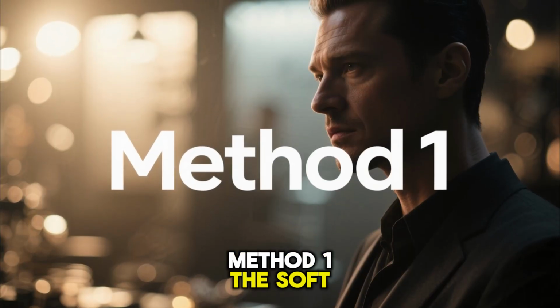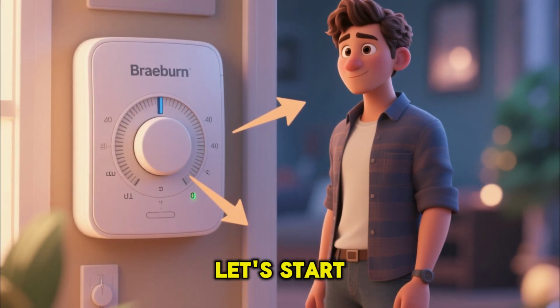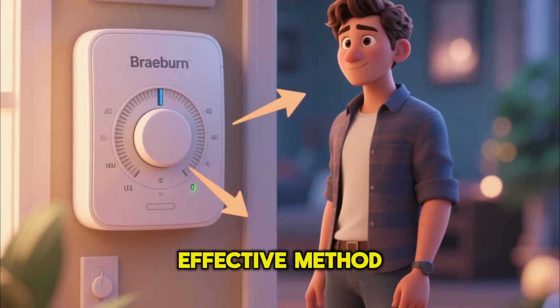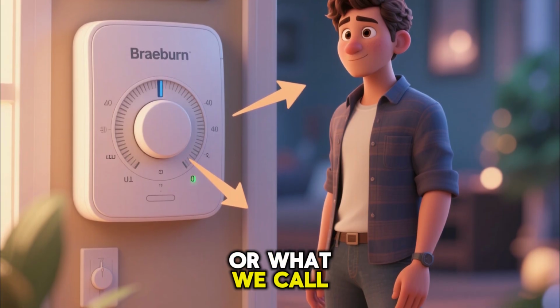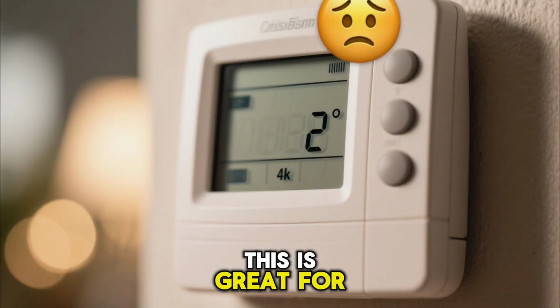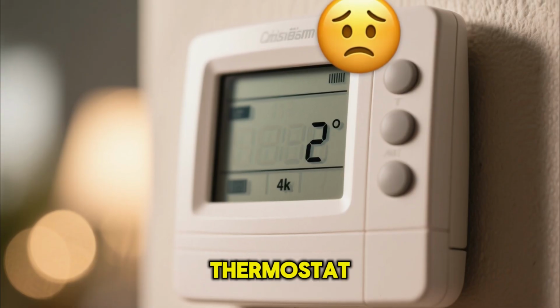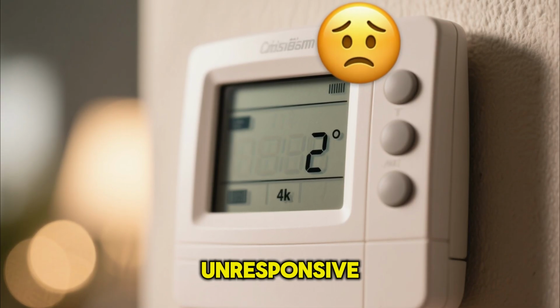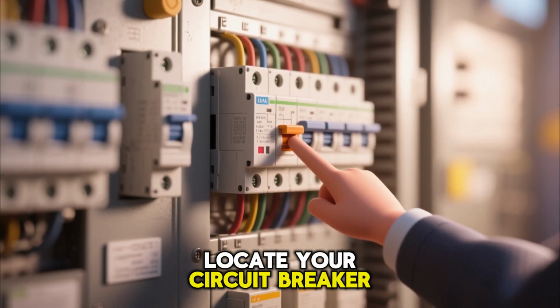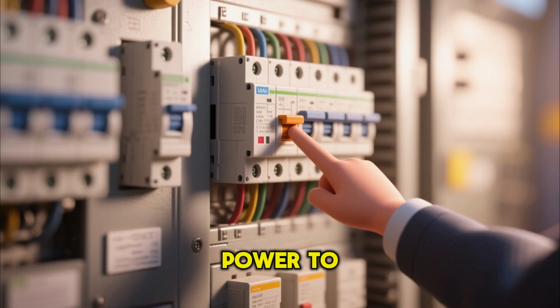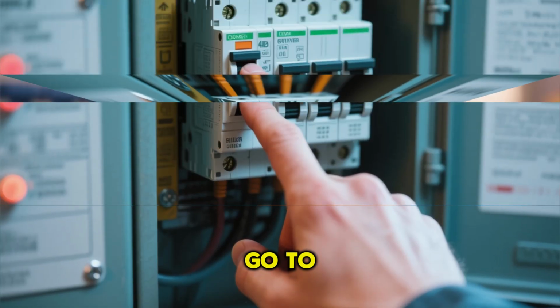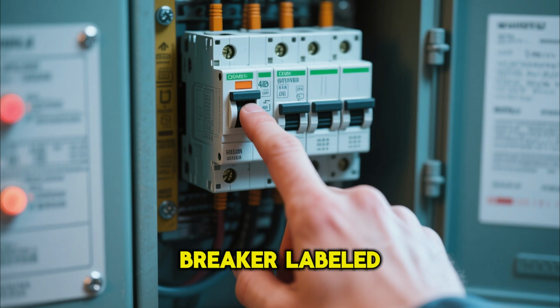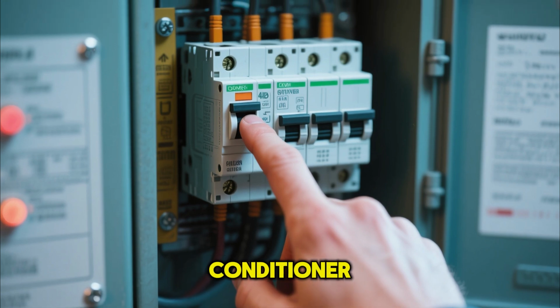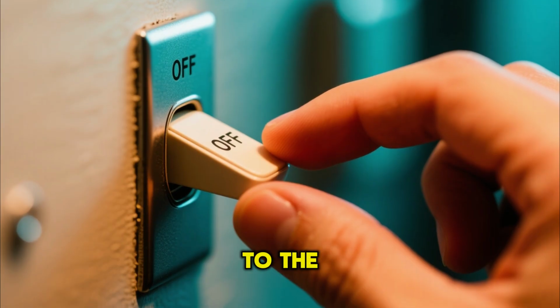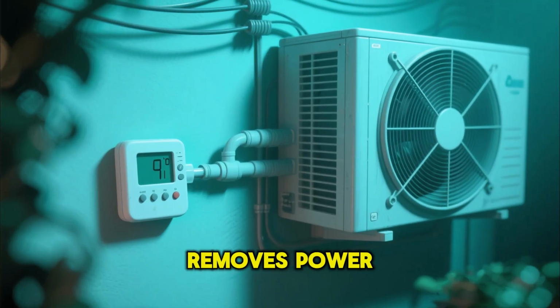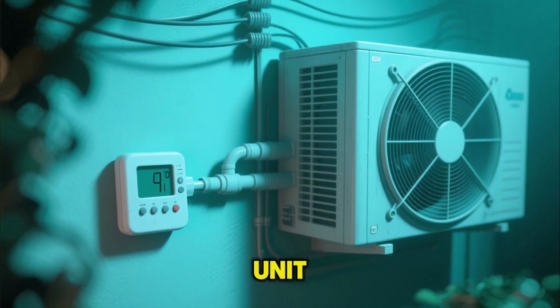Method 1. The soft reset, power cycle. Let's start with the easiest and often most effective method, the soft reset, or what we call a power cycle. This is great for minor glitches, or if your Braeburn thermostat screen is blank or unresponsive. Locate your circuit breaker. The most crucial first step is to cut power to your entire HVAC system. Go to your home's main electrical panel and find the breaker labeled for your furnace or air conditioner. Turn off the power, flip that breaker to the off position. This completely removes power from your thermostat and the connected HVAC unit.